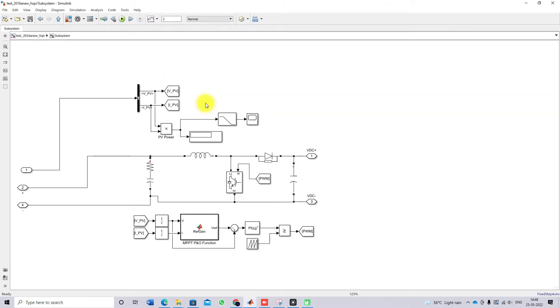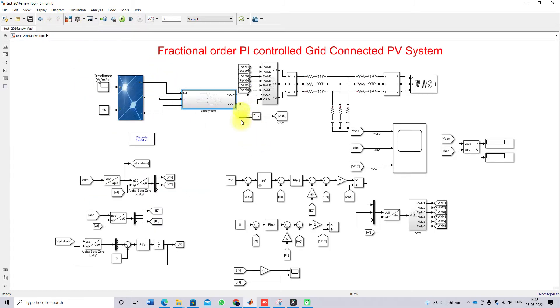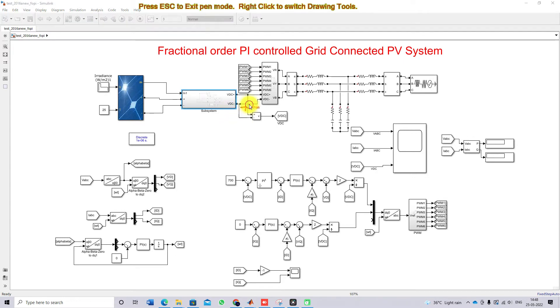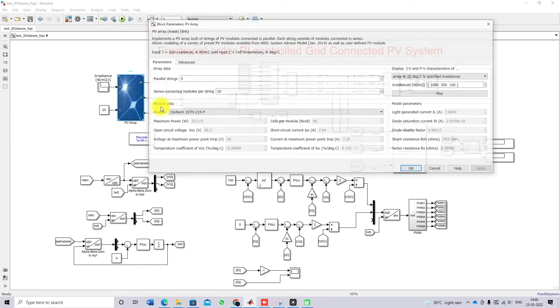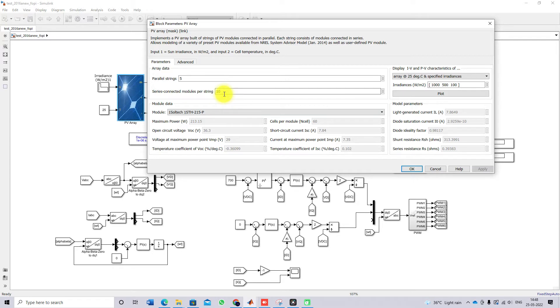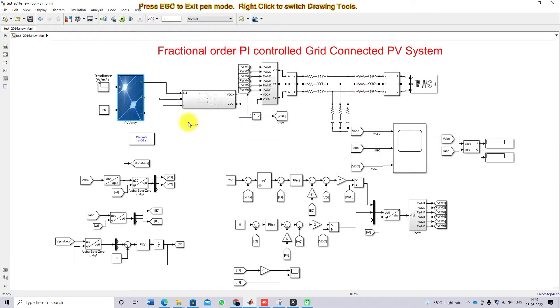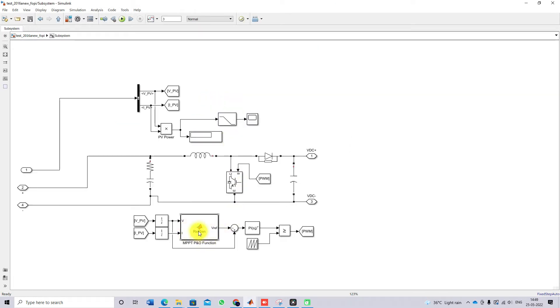Here we are using a boost converter because we need to maintain 700 volts on the DC link. The single panel voltage is 29 volts, and with 10 panels in series that gives 290 volts, which is stepped up to 700 volts by the boost converter. This boost converter is controlled by the MPPT algorithm — specifically we are using the P&O MPPT.